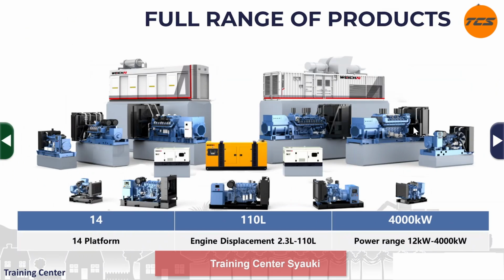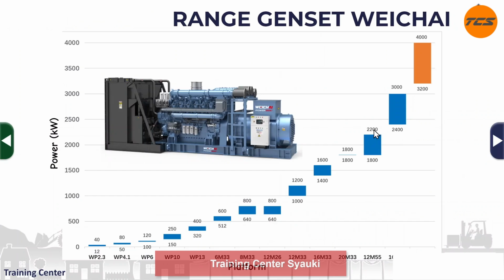For generator products, Weichai has a powertrain division with 14 engine platforms, with engine displacement ranging from 2.3 liters to 110 liters. The power output range covers 12 kilowatts up to 4,000 kilowatts. For example, the WP 2.3 engine platform has a power range of 12 to 40 kilowatts, while the 12M33 covers approximately 1000 to 1200 kilowatts.